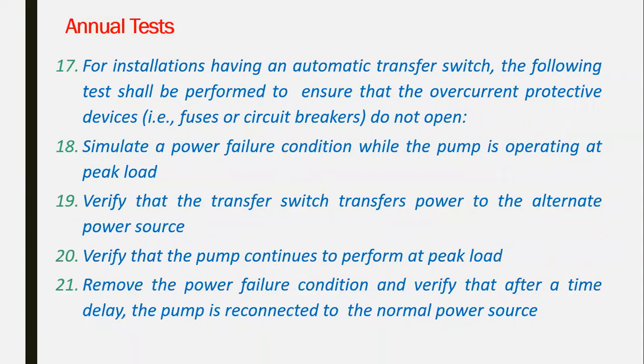When you have an electric pump with an automatic transfer switch installed on the pump, if it is fed from normal power directly from the transformer and it has a standby diesel generator, it should have a transfer switch, and this should be set automatically, not in a manual position. It should be in the automatic position. So we have to test the ATS and the controller, checking that the overcurrent protection device, like a fuse or circuit breaker, does not open.